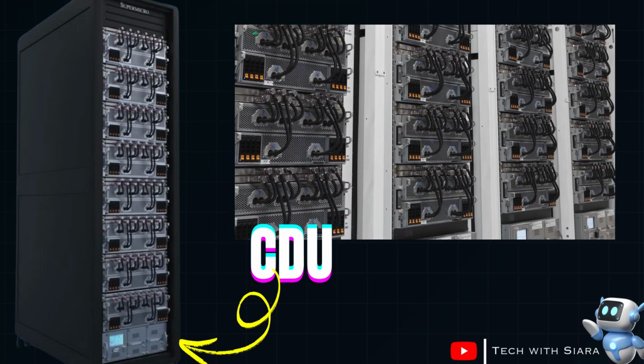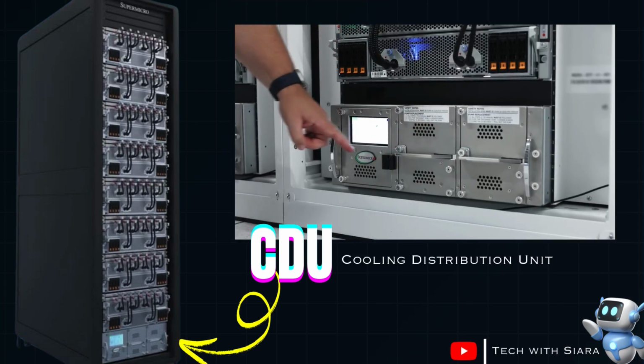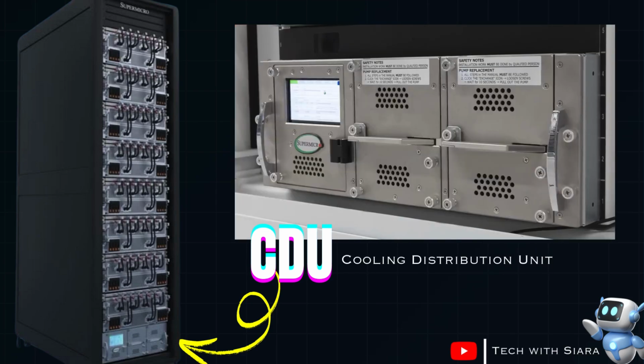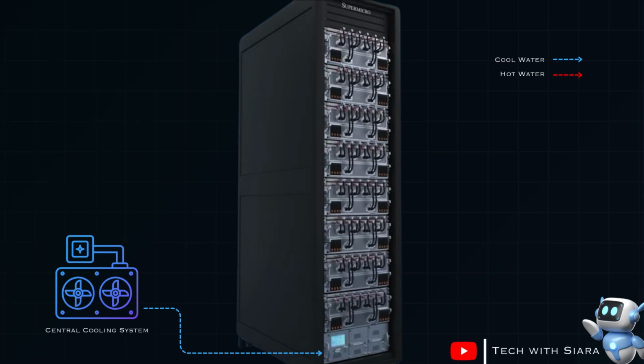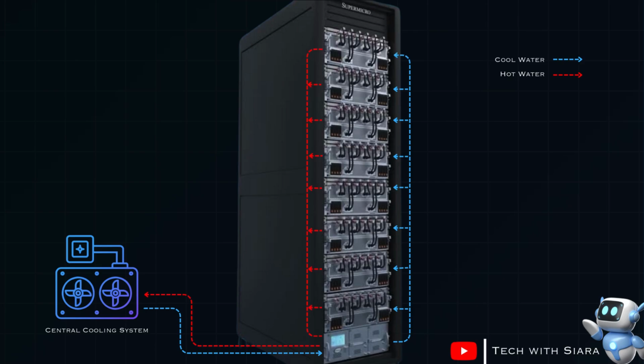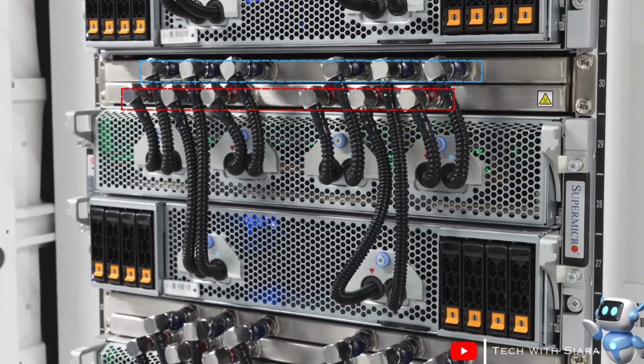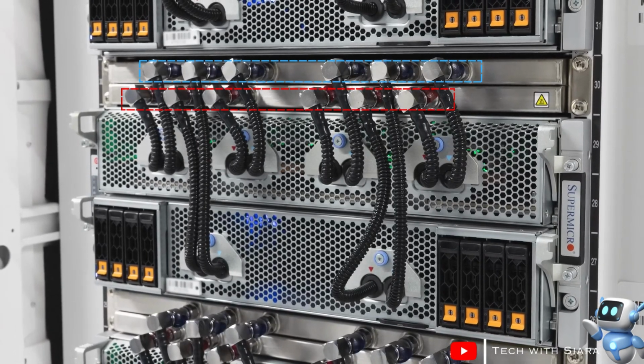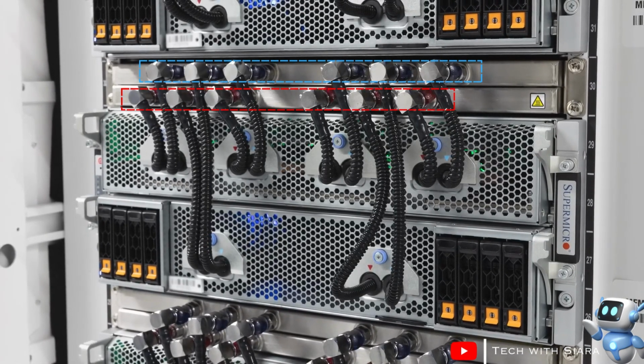At the bottom of each rack, there is a CDU, which stands for Cooling Distribution Unit. The CDU is connected to the central cooling system. It pumps cool water to the NVIDIA platforms, which keeps all the GPUs cool, and sends the hot water back to the CDU. With each of these platforms, you can see blue and red pipes. Blue pipes carry cold water, and red pipes carry hot water.